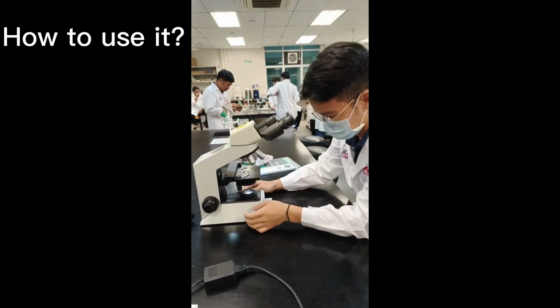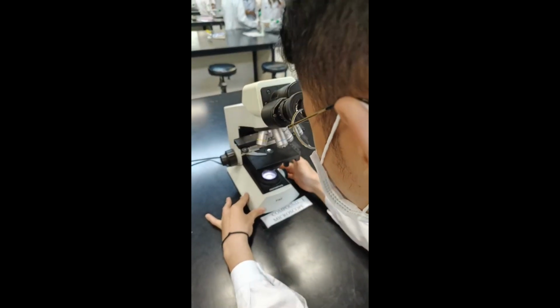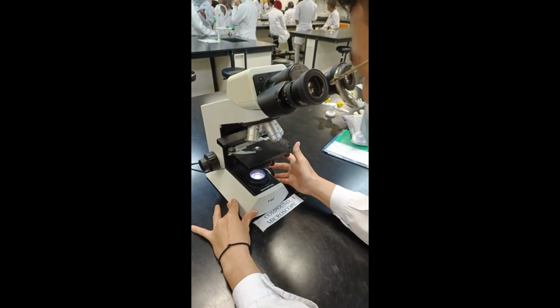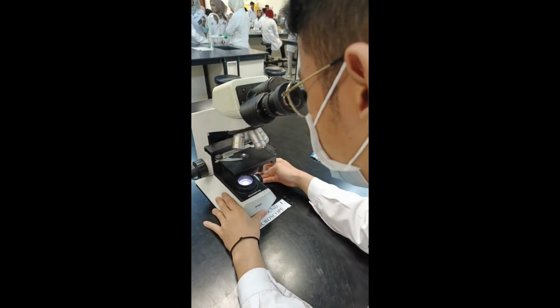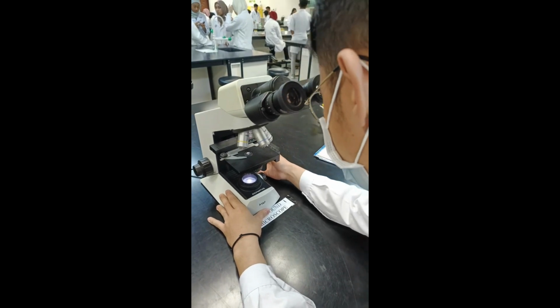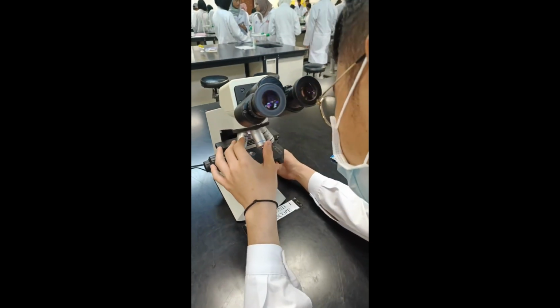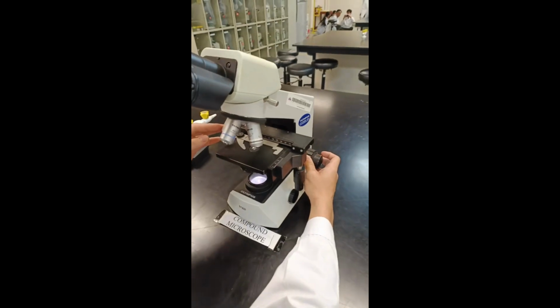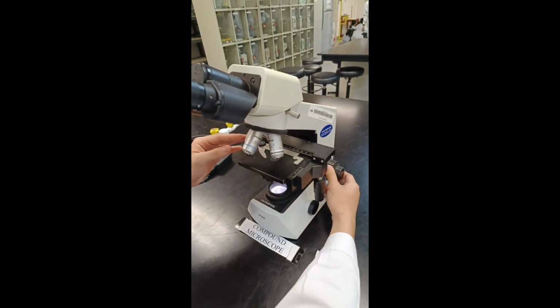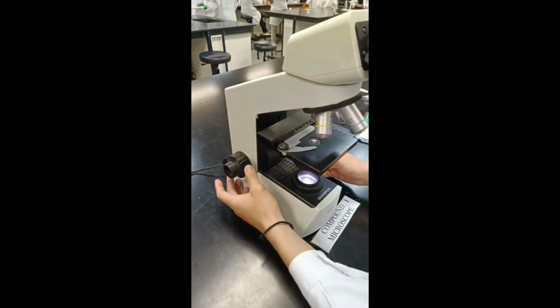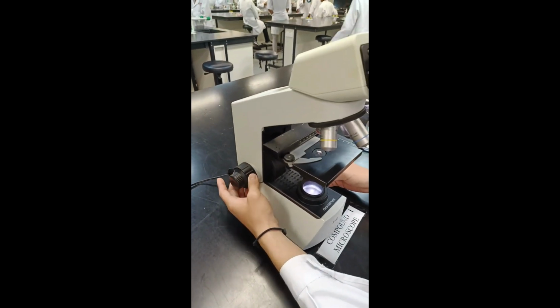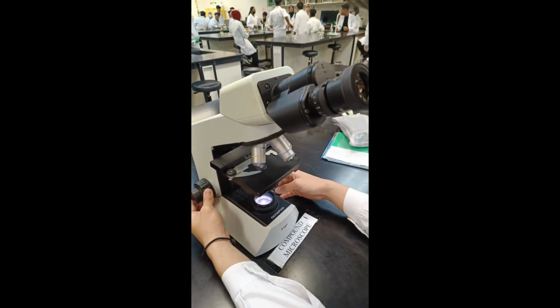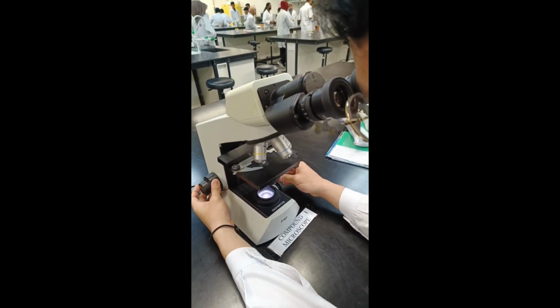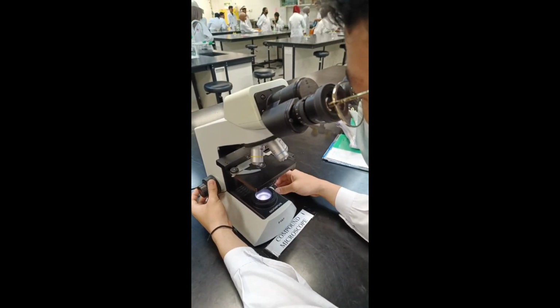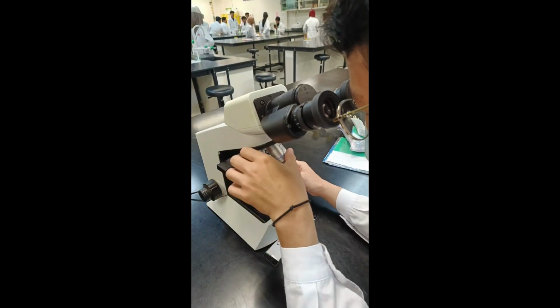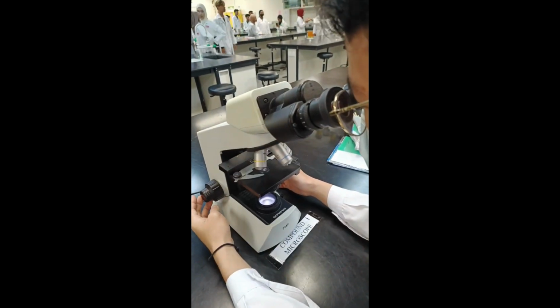First, switch on the microscope. And here is the light source to control the light intensity of the image. The image will be seen through the eyepiece, and we will start from the lowest magnification, which is 4 times magnification. The coarse adjustment is used to adjust the stage, either to lift or lower it. And here is the fine adjustment, which is used to focus and sharpen the image.